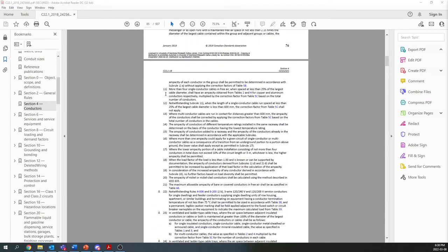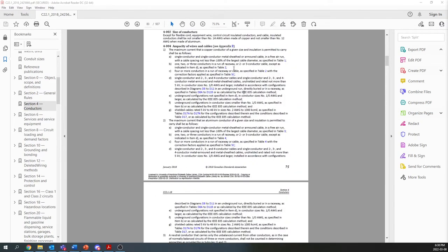Anyways, that's a bit of a sidetrack there, but rule 4-004 is very important. So you don't need to say any more than that. It is very important, and in general it directs you to tables, as you can see here, table 1 or 2 or 3 or 4, depending on if you're using copper or aluminum. And we will go through those tables later. So yeah, that is conductors.